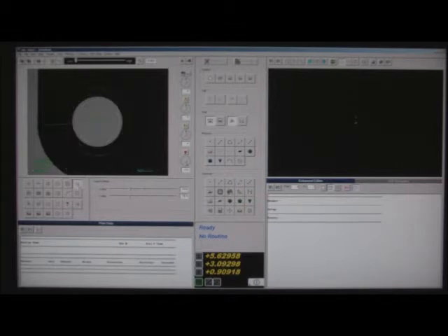The next target we'll look at is the protractor target. The protractor target lets us measure an angle the same way a screen ring would on an optical projector. So I can set it to the edges of whatever I'm measuring and then read either the complementary or the true angle. The next target we look at is a radius target.